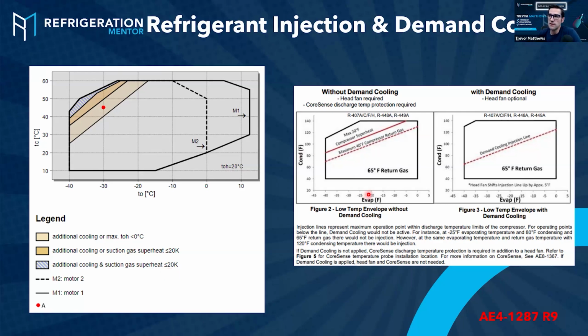Okay. And if we look over here, so that's kind of the Bitzer one. So right now this one here, we're at about 45 SCT or SDT, and we're minus 30 SST. Okay, so that's Celsius. So we go over to the demand cooling for the Copeland one. You'll see the example. Here's the refrigerant. I forgot to say, I think I did 454C for this one. This is 407A, F, H, C, or 448, 449. This says head cooling fan required, so a head fan required, but a CoreSense discharge temperature protection. Back in 2013, I think, maybe it was 2010, I can't remember exact dates, that's when they came out and launched the CoreSense product line. Over 10 years ago, because I worked for them almost 10 years ago.